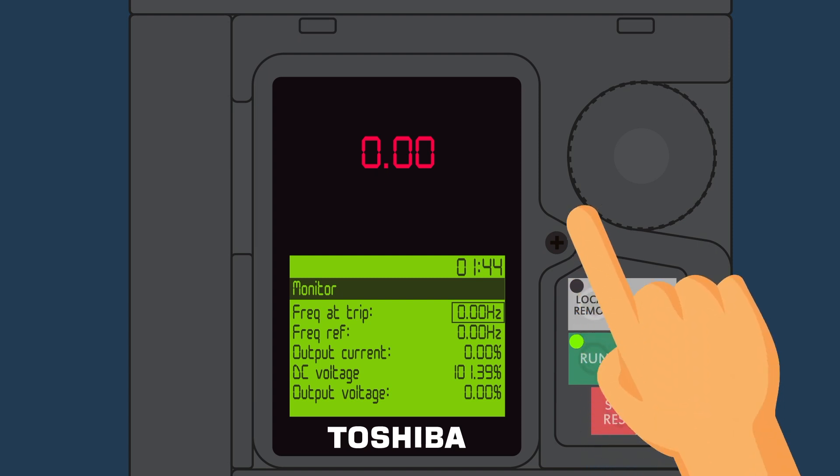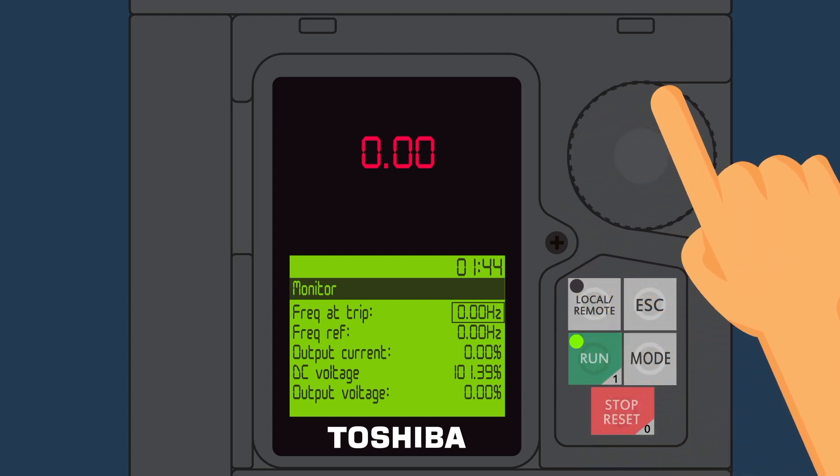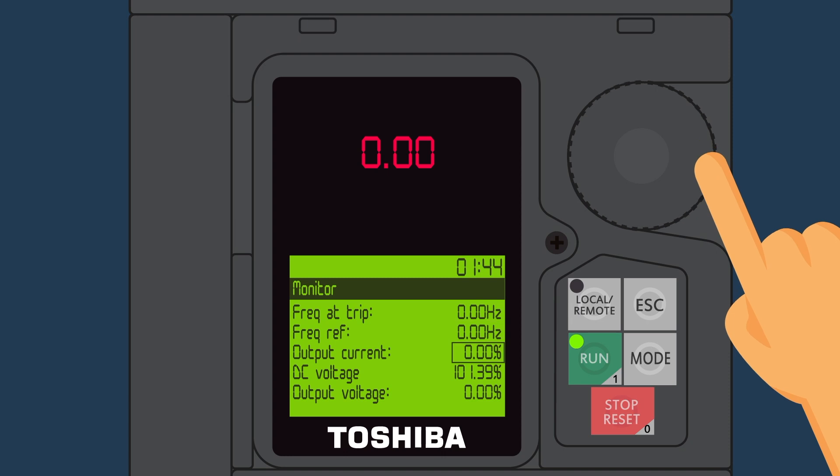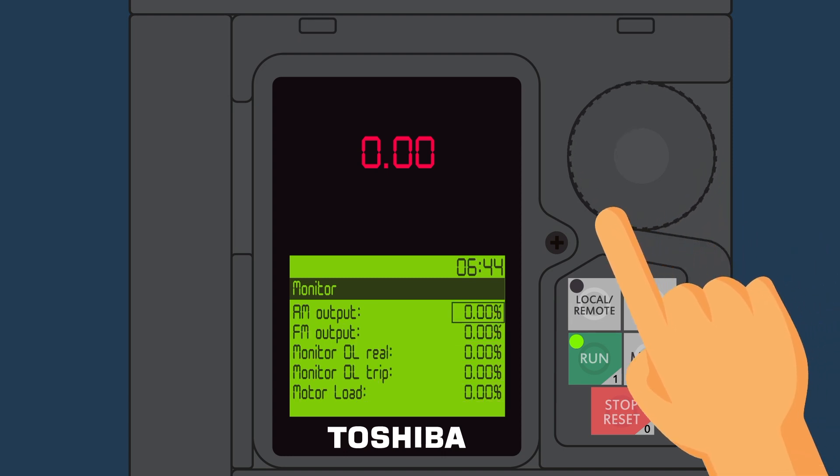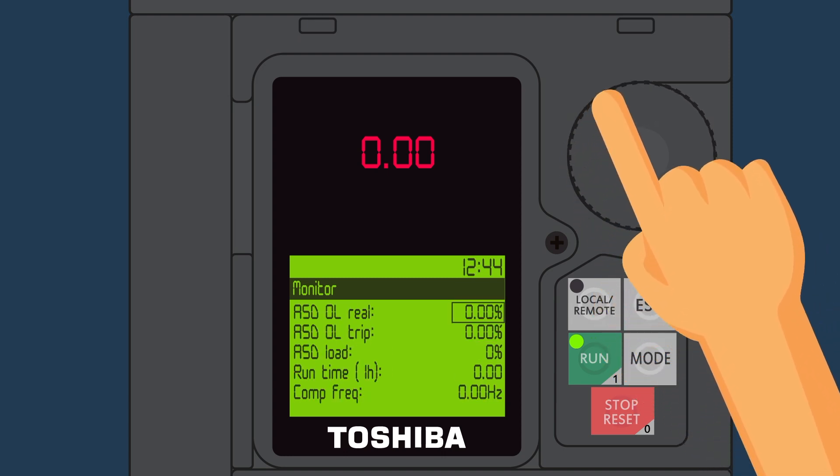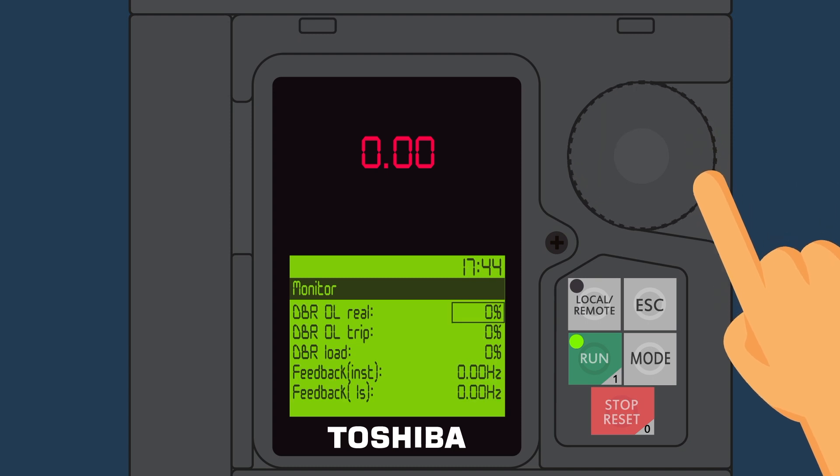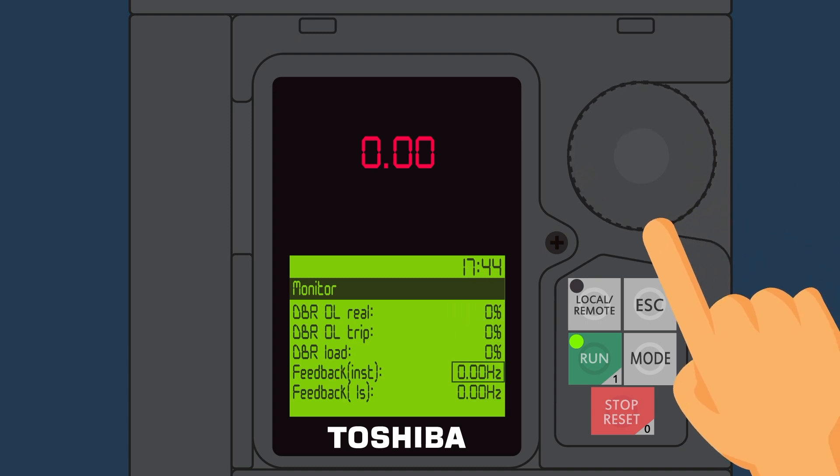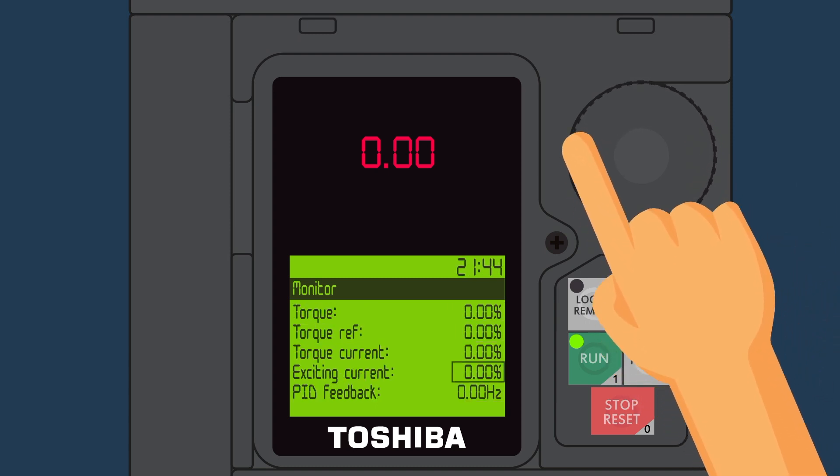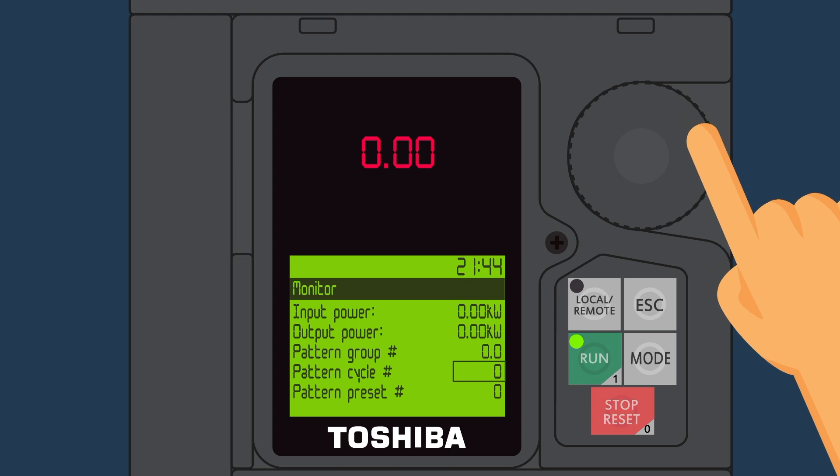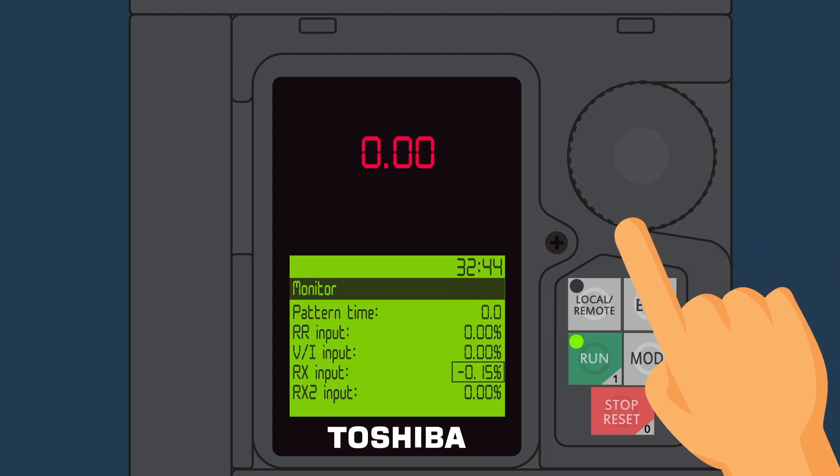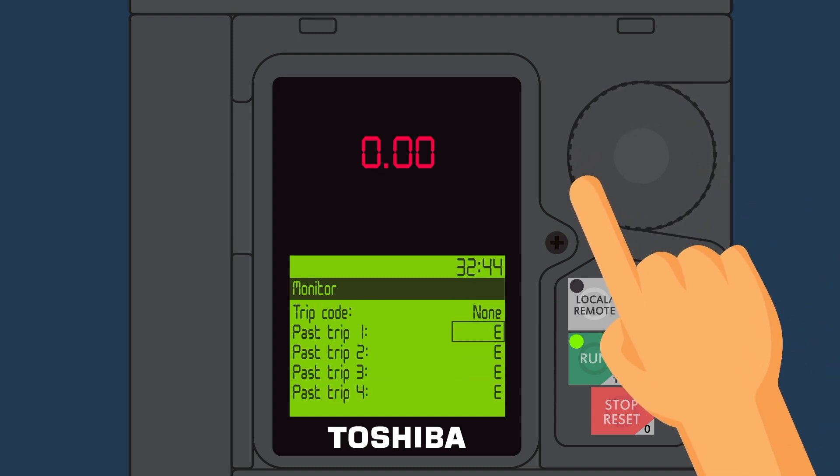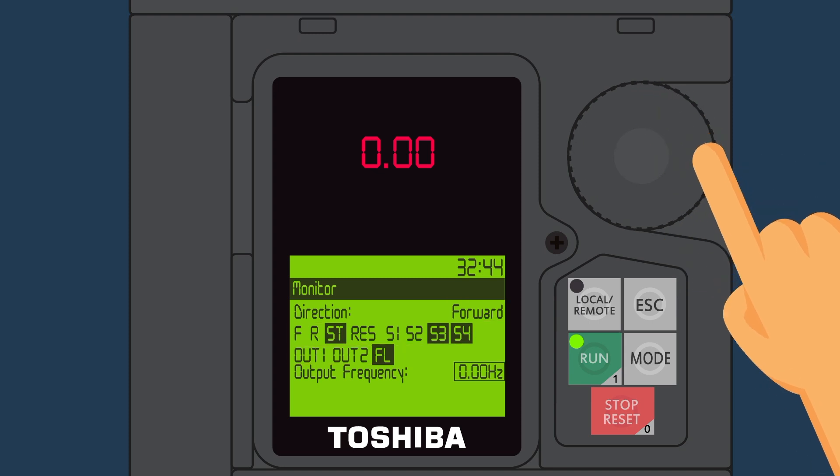Use the rotary dial to access the complete list of monitoring parameters. Things like the output current, DC voltage, last four trips, and terminal status as well as other key information that is useful when starting up, operating, and troubleshooting the drive are available in the monitoring mode of the Q9 Plus.